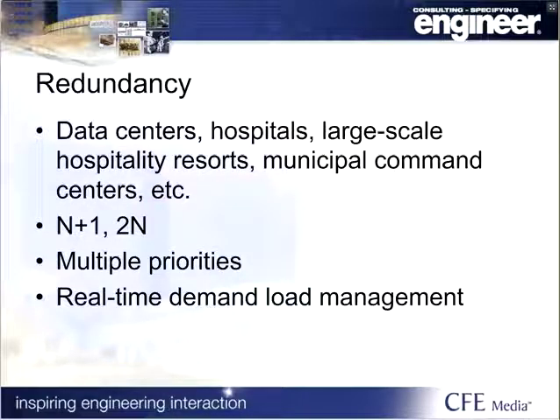Redundancy in the EPS can be very common for facilities where there's an elevated demand to ensure critical systems are not subject to lengthy interruptions due to loss of utility. In some cases, this could be to protect loss of life, such as life support systems in hospitals, and in others to protect against financial loss in a data center or any other large hospitality resort, etc. In an N+1 configuration, the total required capacity is spread over one or more generators, plus one additional generator is installed equal to the rating of the other individual generators. Should one generator fail, the remaining generators will pick up the full load.